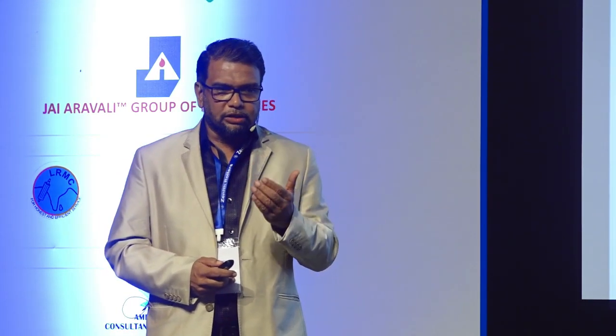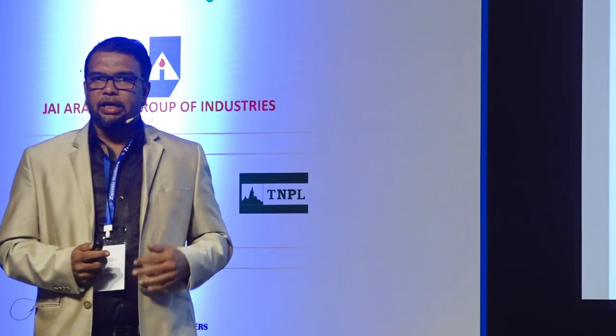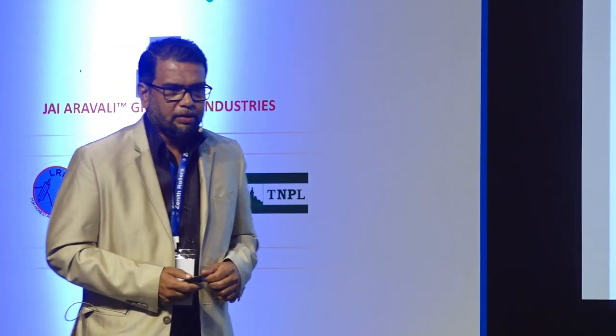The existing supply network is kept intact. Additional heat requirement, if any, above 60 degrees can be fulfilled by using steam. That means we kept our existing system, where steam is supplied for heating the water, intact. The pulp mill effluent has a high temperature, but there are a lot of fibers and other dirt in it, so we wanted to remove them first before feeding it to the heat exchangers.